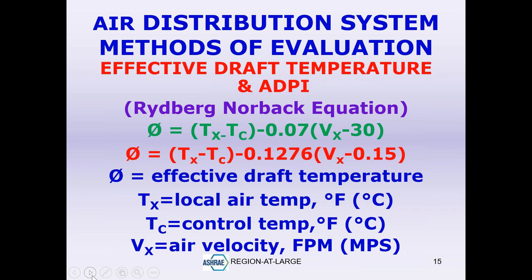There is a method to calculate the Effective Draft Temperature (EDT). The equation — shown in green for IP units and below it for SI units — requires measuring the local air temperature at a particular point (Tx) and the control temperature (the temperature you're trying to maintain in the space, e.g., 75°F). Vx is the air velocity in feet per minute or meters per second. You need to measure velocity at the same point where you're measuring temperature simultaneously.